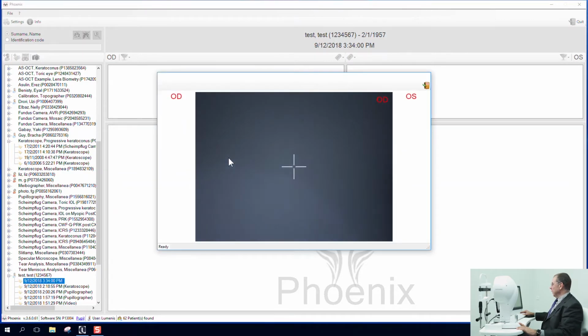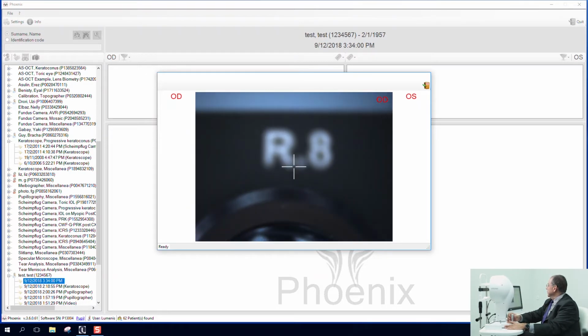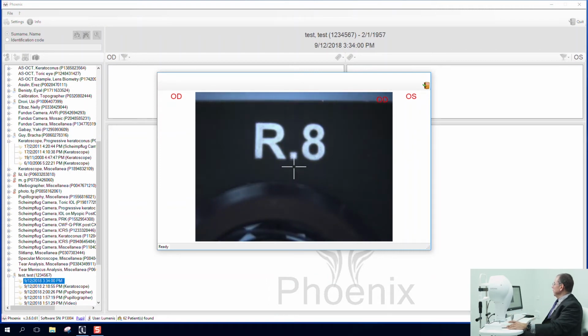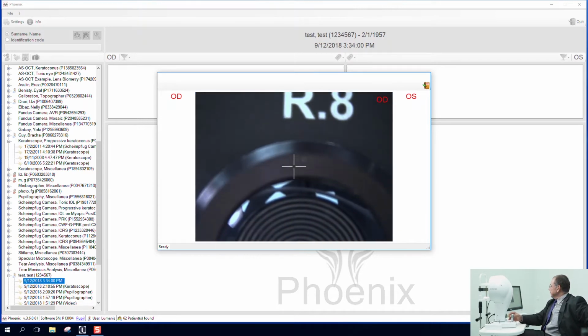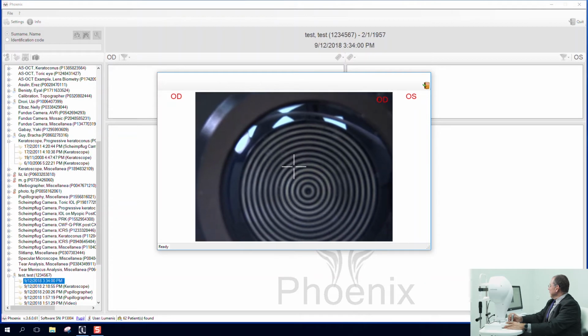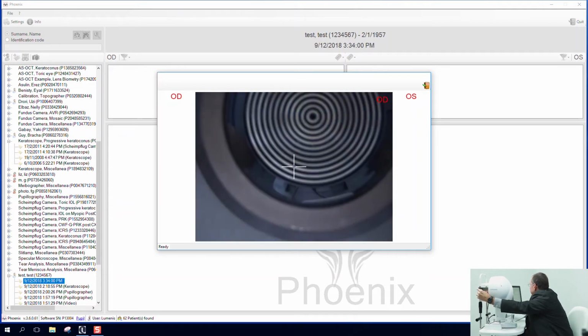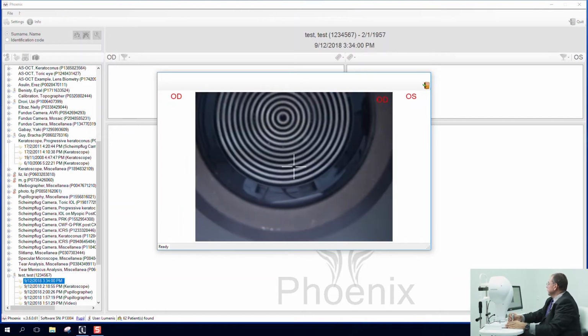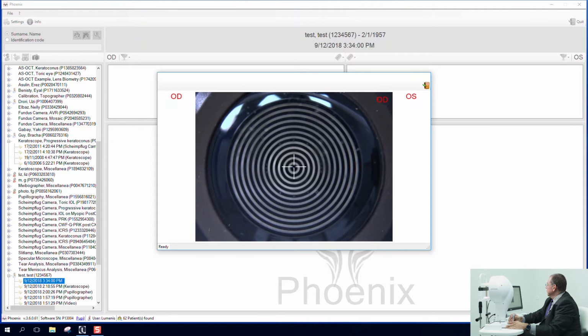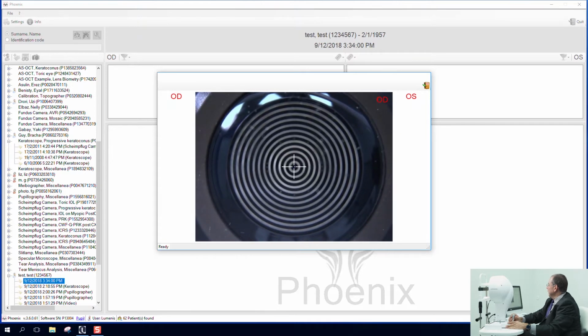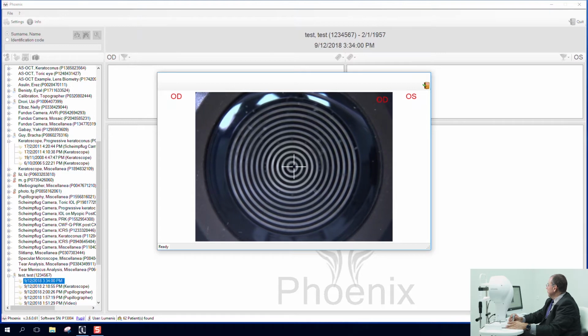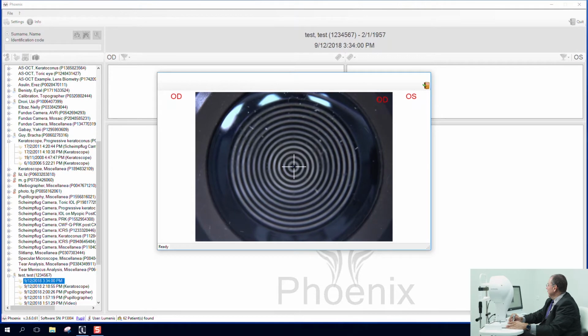Remember, this should be done in a dark room, not in a light room. And what I look for first of all is that it in fact is an 8 millimeter radius. So we're under the 8 millimeter radius. I've noticed that this is a little bit dusty, but otherwise it's pretty clean. We'll raise it up a little bit so we can get to it. And what I'm going to do is exactly as we would normally do a reading on a patient. Get it in focus, bring it slightly back, press the button once, and go forward.